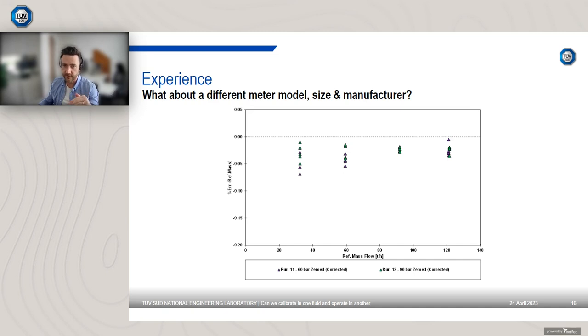It's really just the meter needing adjusted slightly to bring it in line with the zero. However, as most of the data is within plus or minus 0.05%, ultimately it's not really worth adjusting the meter unless you're looking for optimum performance. For that, I would say that's a very good calibration, and it's really just the y-axis scale making it look as if it's not quite as good as the previous calibration. So that's to show you, yes, you can extrapolate. It is possible. So yes, it can be extrapolated successfully, but to do so, you must calibrate at a traceable flow laboratory, and you're ultimately best to use a dynamic pressure correction, which I'm going to touch upon in the coming slides.